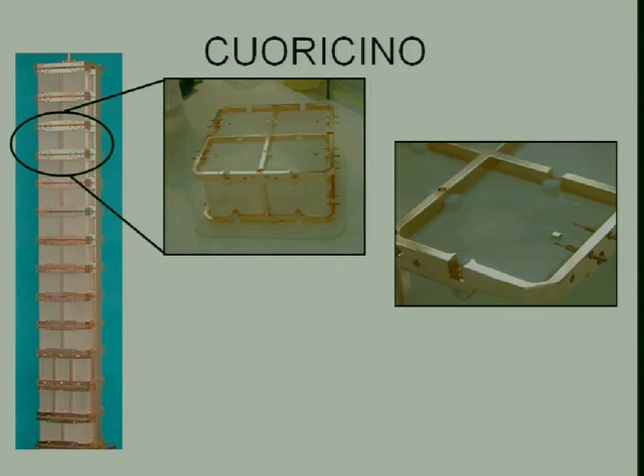This is an interesting little bit of nuclear physics. This is a wafer of very, very pure germanium, which has been irradiated in a nuclear reactor to produce arsenic and selenium and gallium dopants in it in such a way that the germanium now has a temperature-dependent resistivity. And it's glued onto the crystal, and when the crystal warms up, the resistivity of the germanium changes. What you probably can't see here is there are very, very fine gold wires coming in and going out. You run a small current through the thermistor or thermometer. You measure the voltage drop across it. When the temperature changes here, the voltage drop changes. You see a voltage spike. Okay? And that's the basis for this.